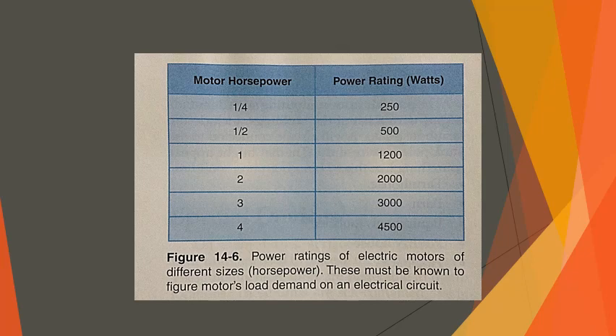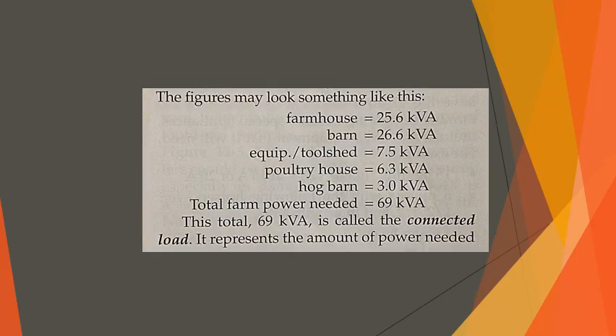Farmhouse equals 25.6 kVA. Barn equals 26.6 kVA. Equipment tool shed equals 7.5 kVA. Poultry house 6.3 kVA. Hog barn 3 kVA. And the total farm power needed is 69 kVA in this case. This total, 69 kVA, is called the connected load.